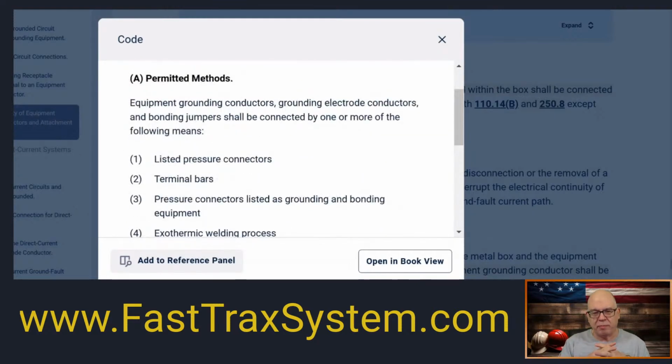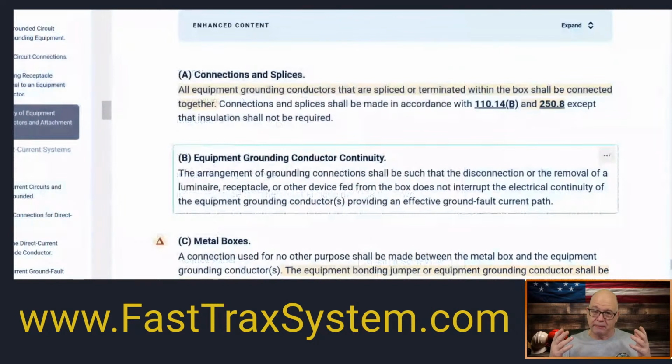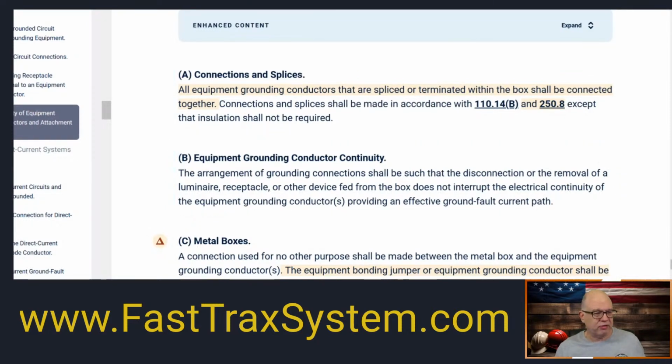But I just find that when you buy the boxes of those, I think they're like 10-32s. I'm not sure of the thickness. Can't remember if that's right. But they're green, so you already know they're typically designed for those threaded ports inside the metal box. So you already know that that's going to be okay. But it doesn't necessarily call out that they have to be green for those. Whereas, as I showed you on a device, it does call out for it to be green. That's kind of interesting. And then the only other green requirement for a screw, obviously, is your main bonding jumper. If you're going to use a screw for that, then that's required to be green. That makes sense? All right.